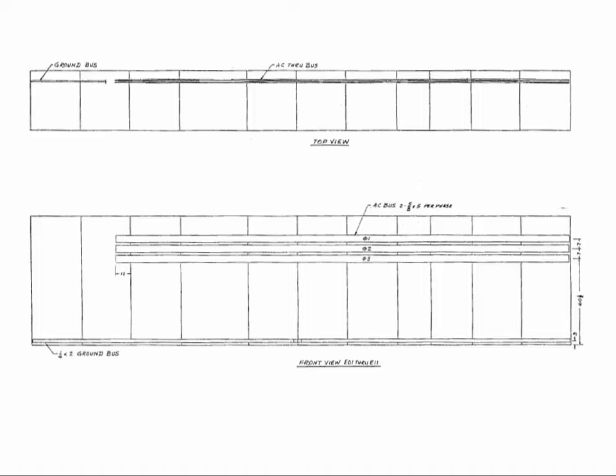All right, so this is just a depiction of the bus bars. Now, the bus bars are just solid bars of copper that run the entire length of the switchboard itself. And these are bolted together, and they form the main distribution. They're designed so that if you have all three generators on the line and they are supplying their maximum load, these bars would be able to handle that full current. So a bus bar is the bus. What we're talking about are these solid bars that are used to distribute electrical power.